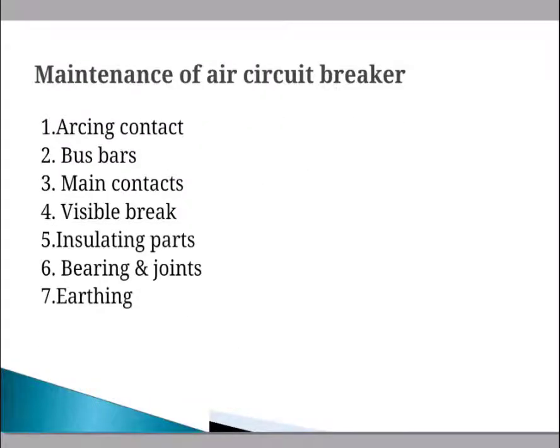For maintenance of the air circuit breaker, first inspect the arcing contacts. Clean the contact surface with fine cloth and petrol. Do not lubricate them. This is carried out quarterly.